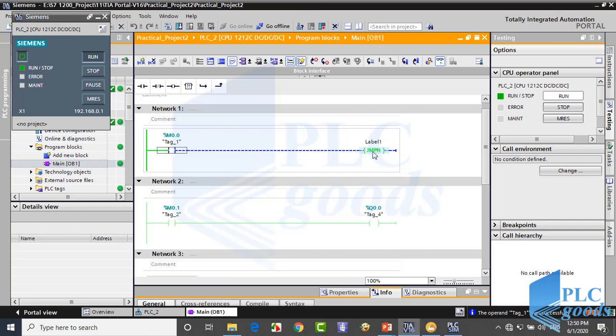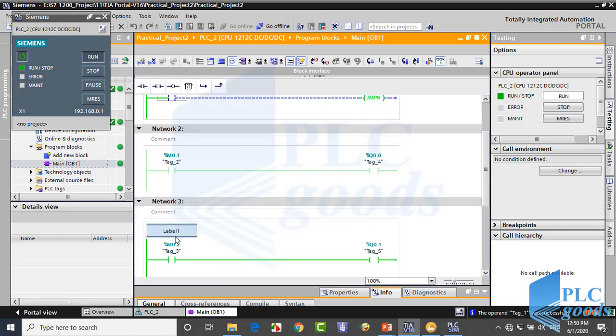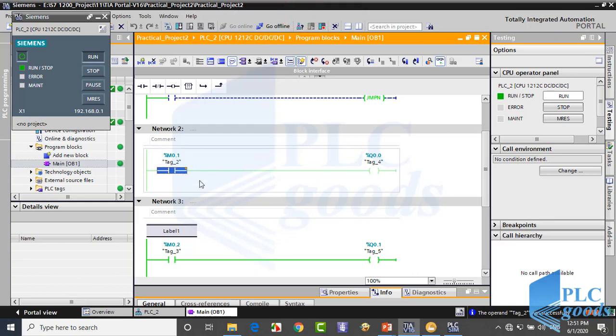At this time, the program jumps to label one, which is placed in the third network, so the second network won't be executed. Pay attention — jump and label instructions must be in the same block, and it doesn't matter where the label is used. The jump direction can be towards higher or lower network numbers.